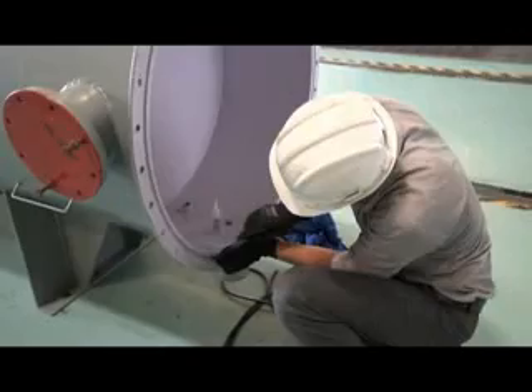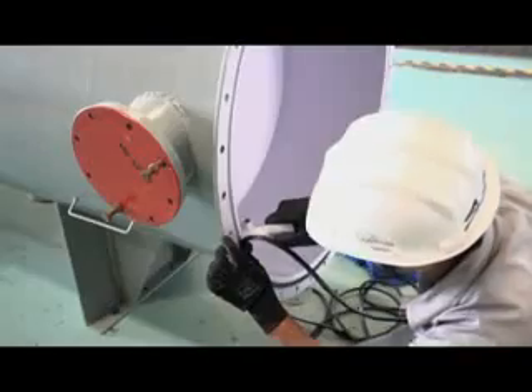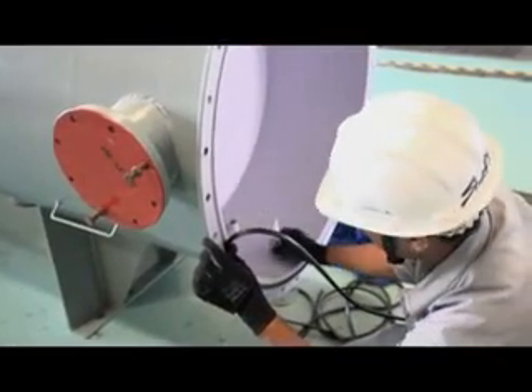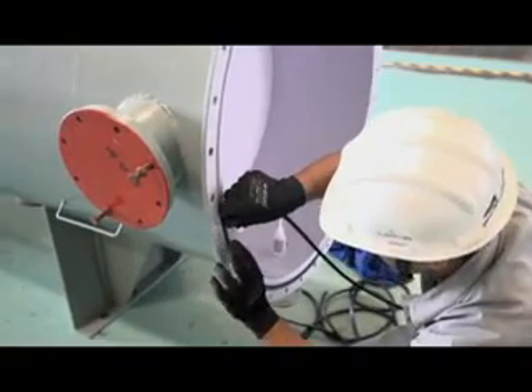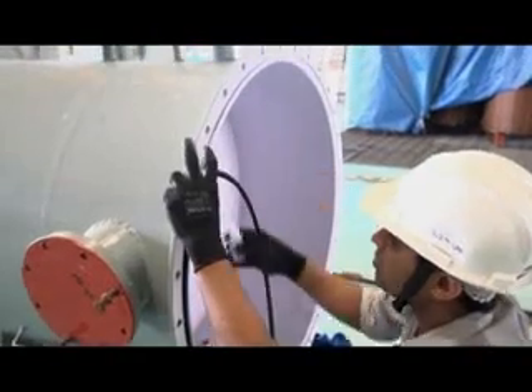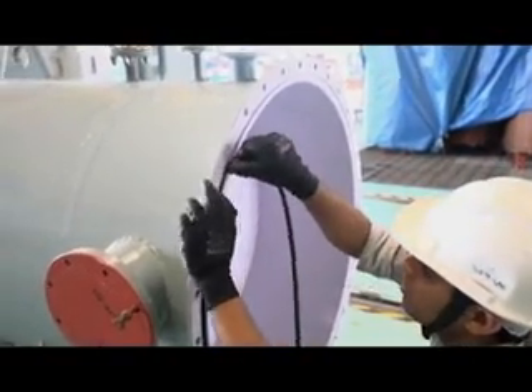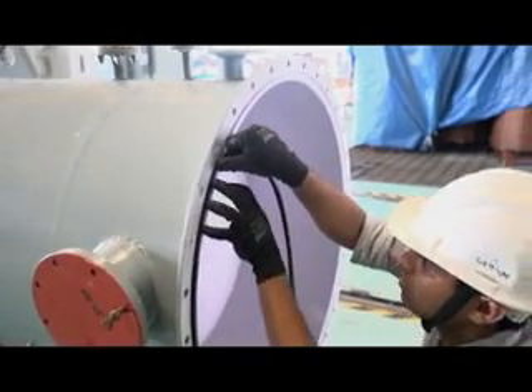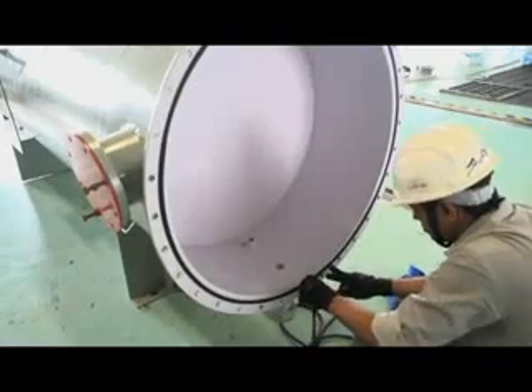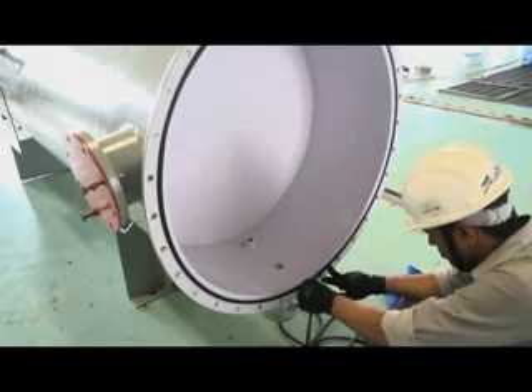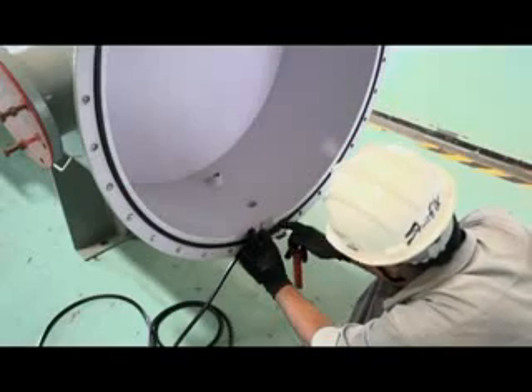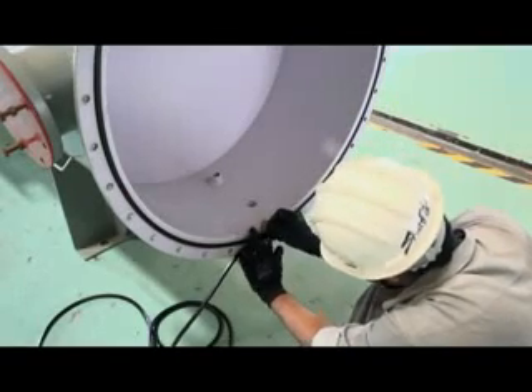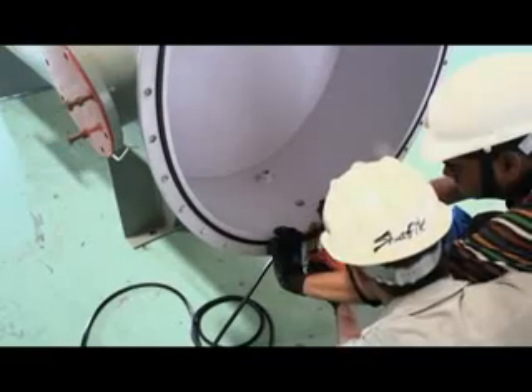POLG is prismatic oil level gauge made with glass to display the oil level in the conservator tank. Fitting of this glass is very simple with gasket, hardware and steel support with maximum, minimum or normal marking on this steel frame. This is an additional device to monitor the oil level in the transformer.